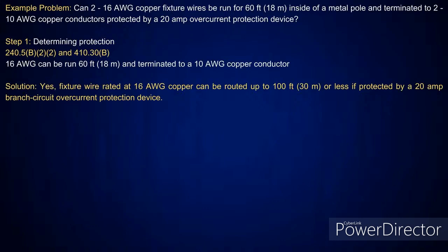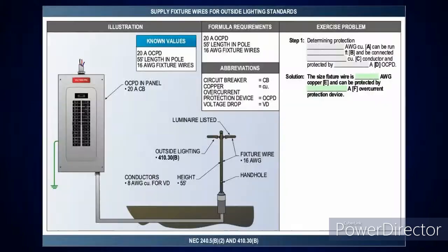Well, and see, here's a good one. What if I'm inside a pole? I've got two number 16 copper fixture wires that run 60 foot inside the metal pole and terminated to two number 10 copper conductors protected by a 20 amp overcurrent device. Can I do that? Well, yes, you can do that, because if you go look at 240.5(B)(2) and also tie that in with 410.30(B), they're going to tell you those number 16s can be run that 60 foot and terminated to a number 10 conductor. But I can see what you're saying. Some say I can tap here and go up and feed all this. Well, I look at it more as they're nothing more than fixture wires.